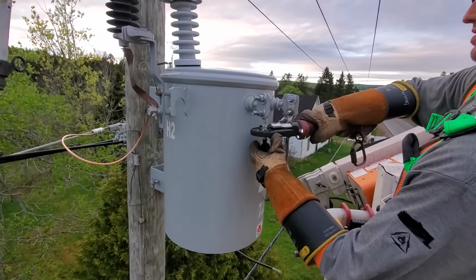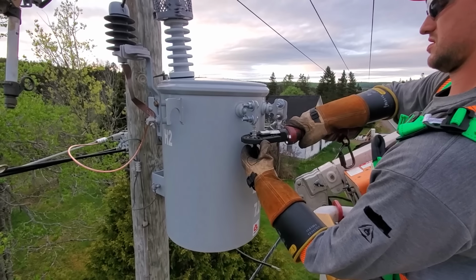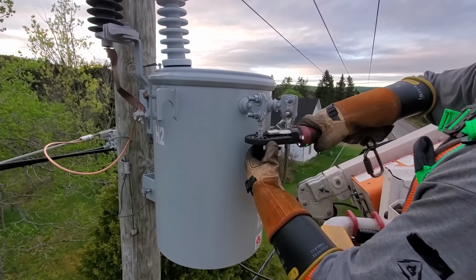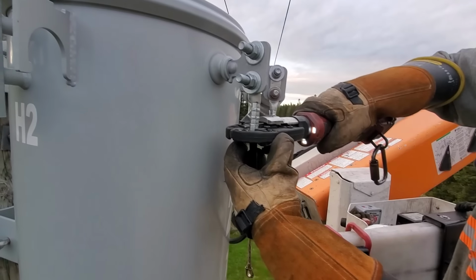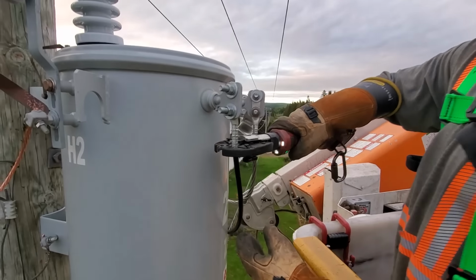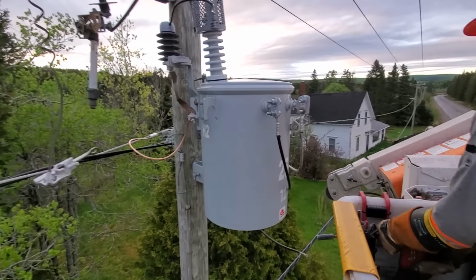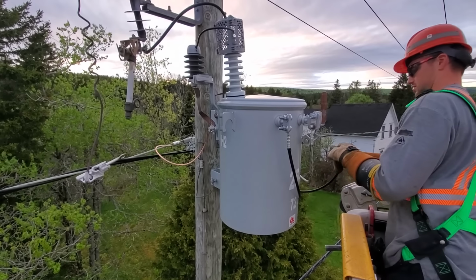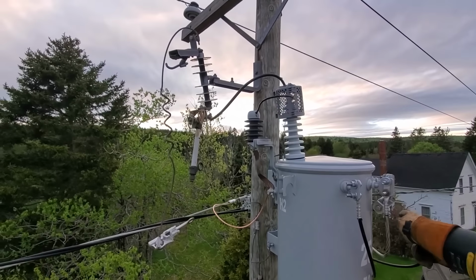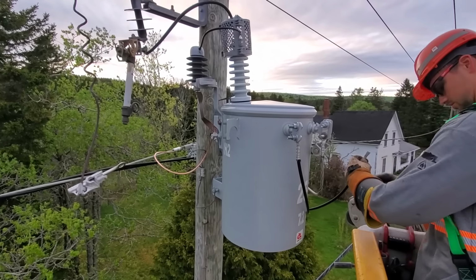So unlike compressing a sleeve, you don't have to rotate the press with every crimp. It is going to start to banana a little bit, but not enough that it's going to bother anything. You'll also notice the old transformer, it was blown. Fuse blew, we came, refused, closed it, blew again.